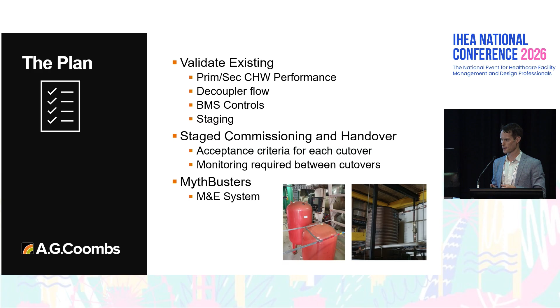So what did we learn? The focus on commissioning planning was absolutely paramount on this job, and I think it set us up for success. We agreed with WAPAC and VAE exactly what they needed to do before we started functionally testing and before we went into operational monitoring. That included pressure testing, flushing the pipework, chiller commissioning, pump commissioning, BMS point-to-point testing, and sub-main circuits. Everything was documented, submitted, reviewed, and then we went into scenario testing.